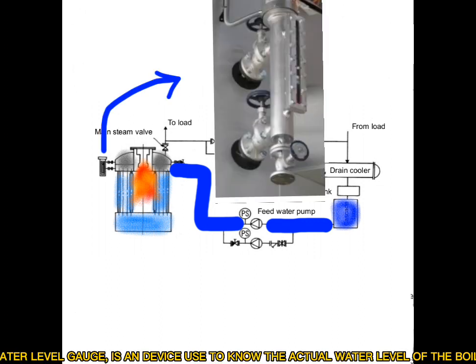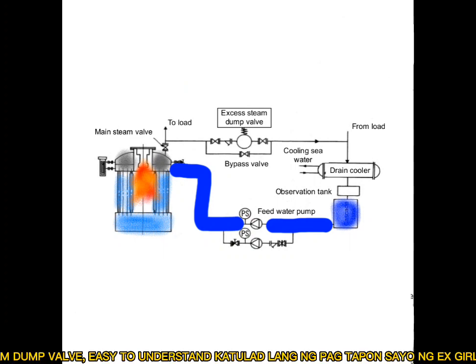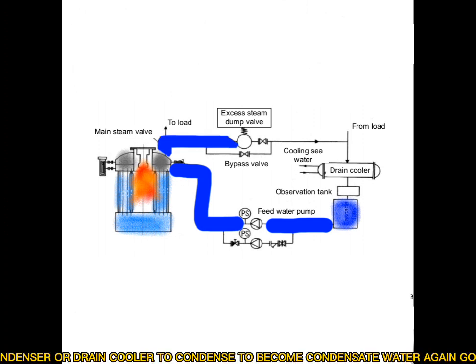The boiler water level gauge is a device used to know the actual water level of the boiler water. When the produced steam is already stable, we can now use the steam for heating tanks, jacket water preheat, and other usages of steam. The excess steam dump valve is used to dump excess steam to the atmospheric condenser, to condense it and become condensate water again, going back to the cascade tank, and the system repeats itself.